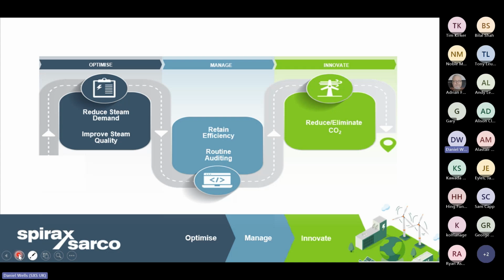For example, our client's boiler could be producing 10,000 kilograms of steam per hour today. But the processes may actually only require 7,000 kilograms of steam. So if we can reduce the capacity of the boiler, or if we can reduce the mass of steam that the boiler needs to produce from 10,000 to 7,500, then we've already made a significant leap forward in reducing our cost of steam, our cost of gas, and reducing those carbon emissions. So that really is the first link in the chain, the first step that we're going to explore in some detail today. It's the optimise piece. We need to understand how and where those inefficiencies exist in an existing traditional steam system and understand what the payback, what the benefit is going to be if we can instigate those improvements.